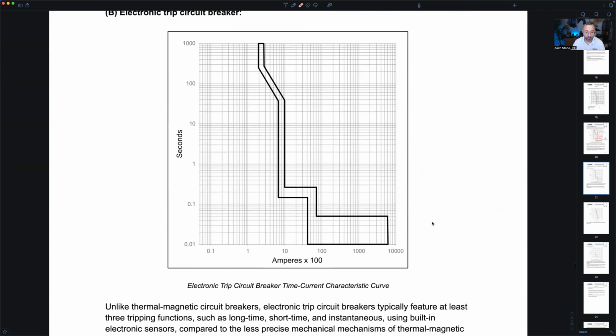How many different trip regions do I have here? Quite a few, don't I? Look, here's our instantaneous trip region. So we still have an instantaneous trip. Here's another trip region. This would be probably our short time delay trip region. And look at this. This is like a long time trip region. So how many trip regions? See if I can draw a rectangle. How many trip regions does this device have? We got at least three, right? Way more than two.